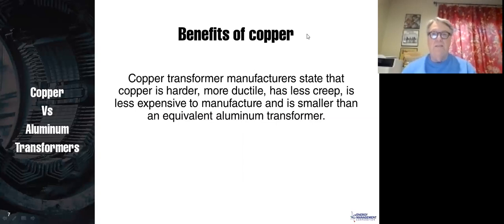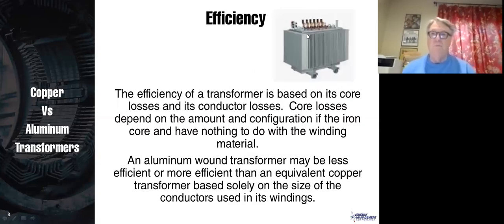Now, that less expensive to manufacture is almost never true. People have switched to aluminum primarily because the aluminum is less expensive to manufacture. Let's look at some of those other claims. First of all, efficiency. The efficiency of a transformer is based on its core losses and on its conductor losses. So the core losses depend upon the iron core, that silicon grain-oriented steel inside the transformer. They have nothing to do with copper or aluminum, and therefore they basically are equivalent.